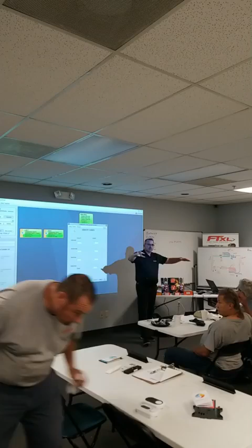This is a unique scenario, I just want to tell you what it is, we won't go too deep into it. If you have some VVT zones on the perimeter of a building that have baseboard heat, and you didn't want those zones sending their heating demand back to the rooftop - you only wanted the core zones to call for heat - we could set this up so we give them the right to vote for cooling, but not the right to vote for heating. Then we give the core zones the right to vote for both heating and cooling. That's what this is for. Most of the time you're gonna do this, and that's it.